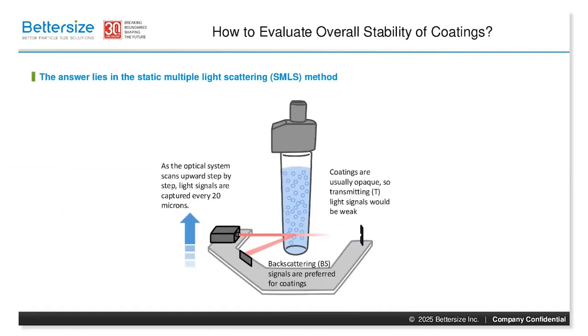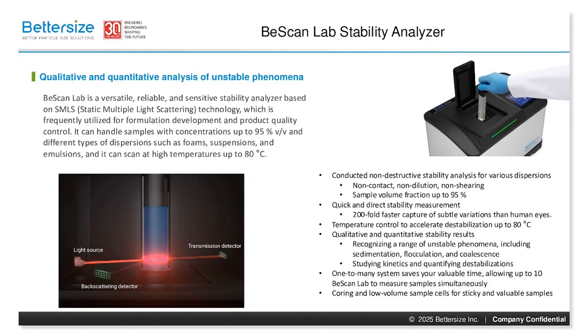To analyze the stability of coatings and other suspension systems, Static Multiple Light Scattering, or SMLS, is a powerful, non-destructive, simple, and fast technique. The BeScan Lab Stability Analyzer, based on SMLS technology, provides quick and direct stability measurements for coating systems.